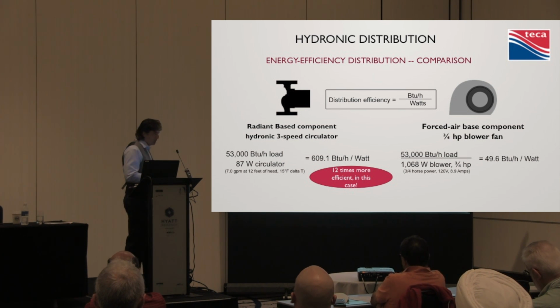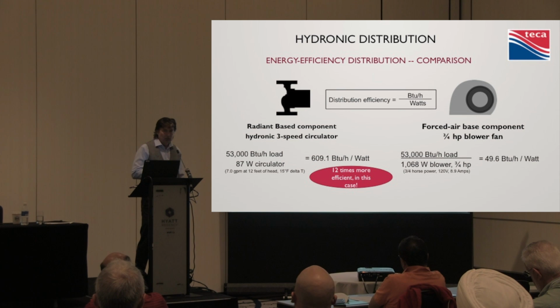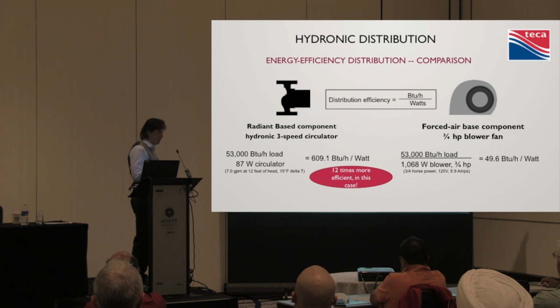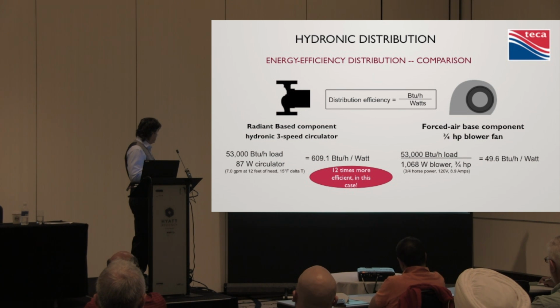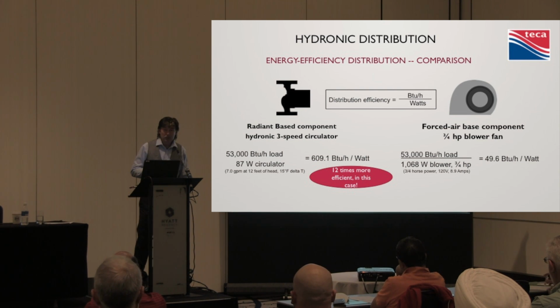If we think about the energy it takes to move water, there's a reason that water is used to move energy. It is good at moving energy. It's been used for years. I mean, when you consider a power plant, what do they cool it with? Is it air or is it water? I can guarantee you it's water. So your typical radiant-based 3-speed circulator to move 53,000 BTUs. Now what is that? Maybe a 3,000 square foot house around here? You could circulate that whole house with one of these.